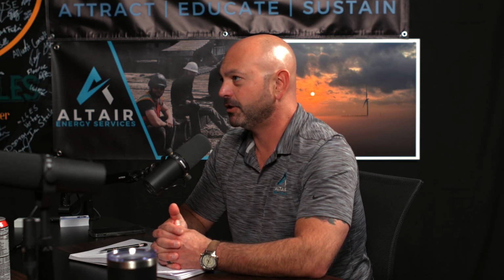Oh, yeah. Joe Chacon, Podge, talks to me about this all the time. Power quality. And he's very supportive of power quality tests on transformers. He goes, I don't care what the nameplate says. Let's go find out what it's really doing. So, and that was another point that I made for the job that we dispatched for you guys, right? Because we identified one transformer that had a tap changer that wasn't functioning. And the tap changer basically changes your incoming voltage, and it can affect your secondary voltage, right?